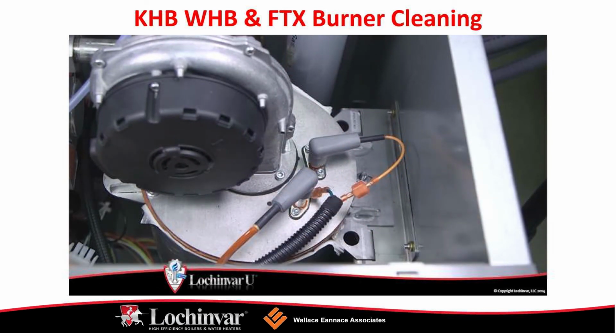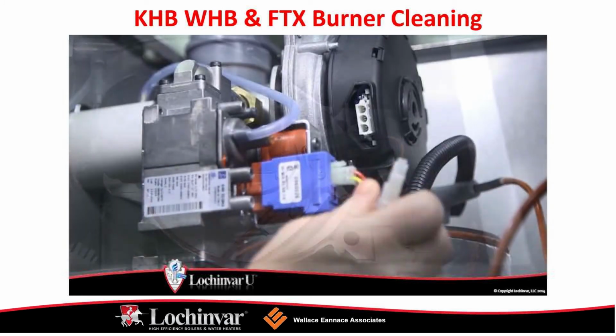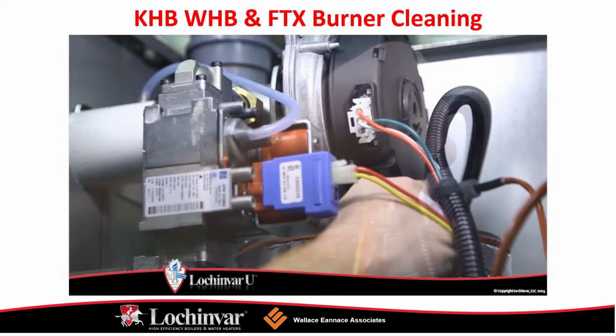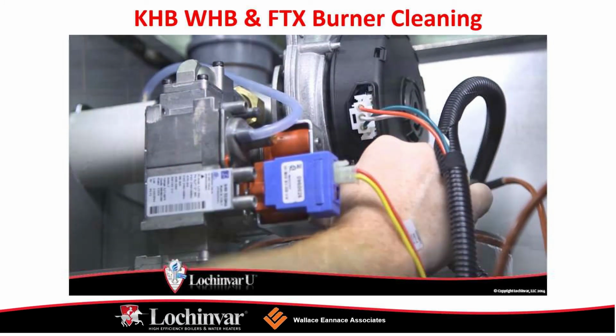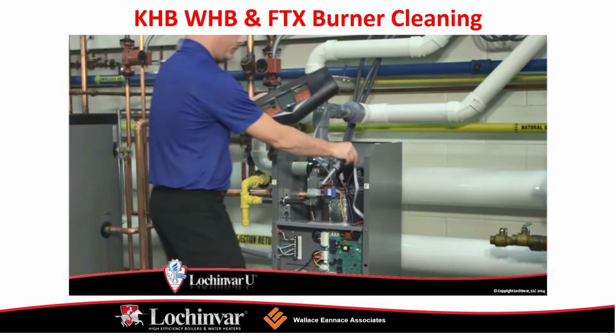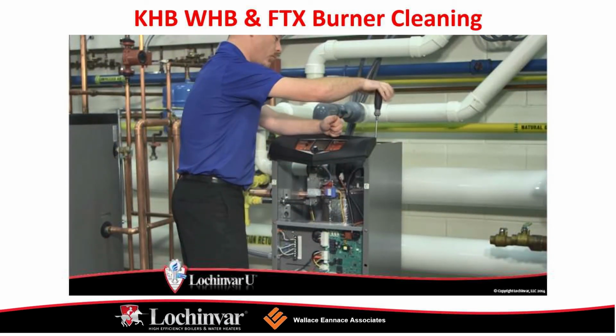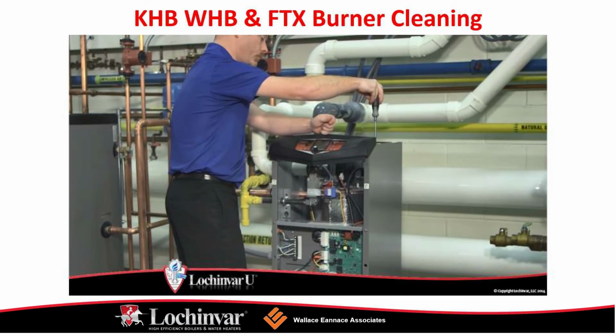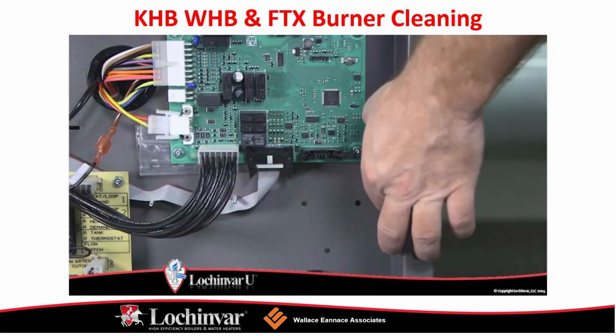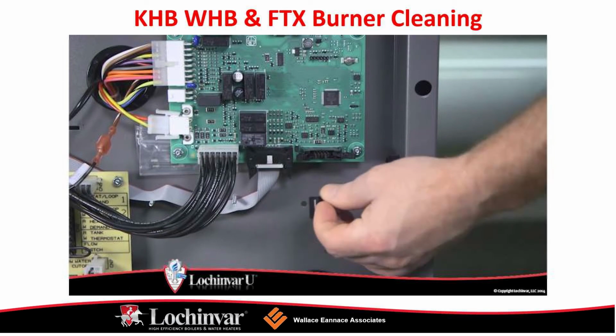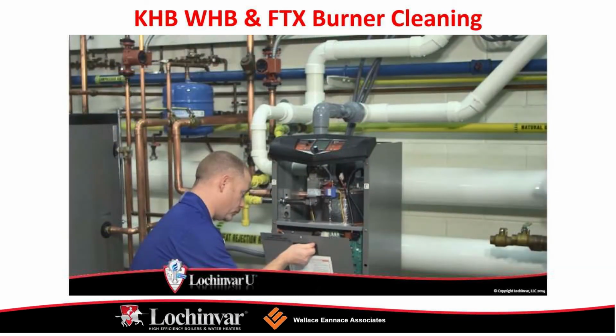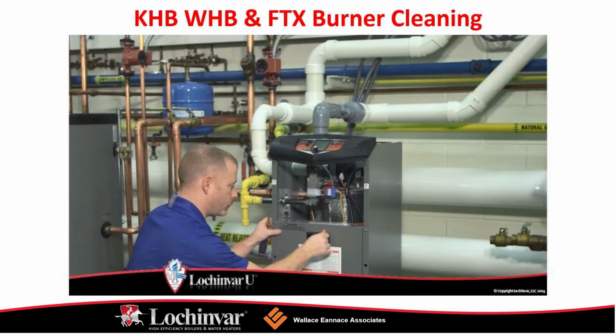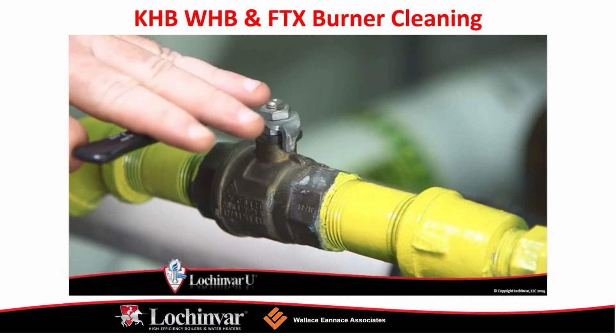Now reattach the burner to the heat exchanger door. And reinstall the refractory. Reattach the igniter and flame rod to the heat exchanger door as well. Then, replace the heat exchanger door and secure it to the heat exchanger.